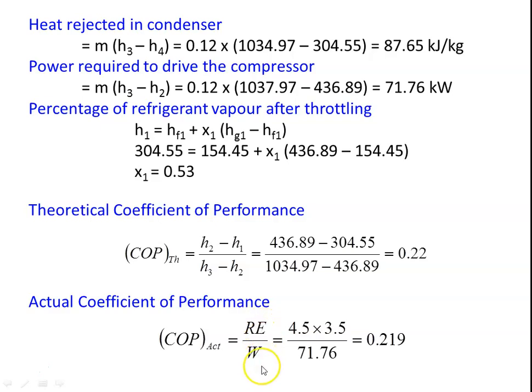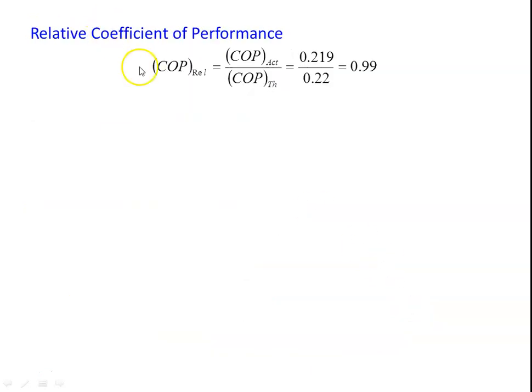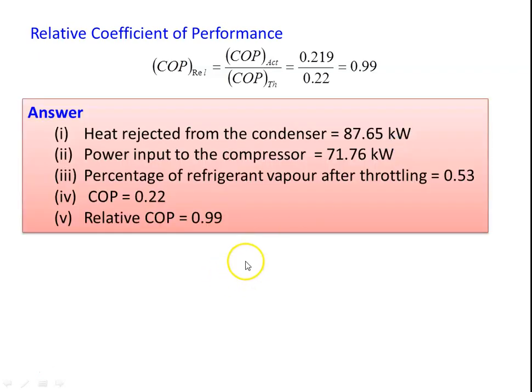Actual COP = refrigeration effect / power input to compressor = (4.5 × 3.5) / 71.76 = 0.219. Relative COP = actual COP / theoretical COP = 0.219 / 0.22 = 0.99. Answers: heat rejected from condenser = 87.65 kW, power input to compressor = 71.76 kW, percentage of refrigerant vapor after throttling = 53%, theoretical COP = 0.22, relative COP = 0.99.